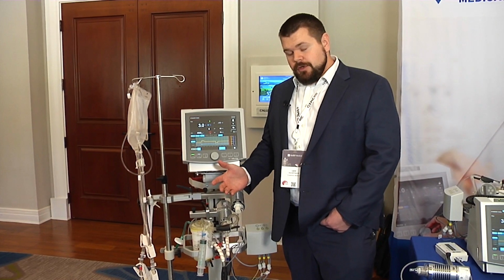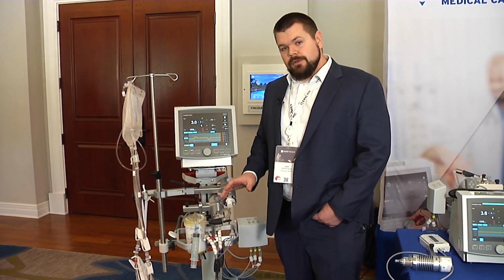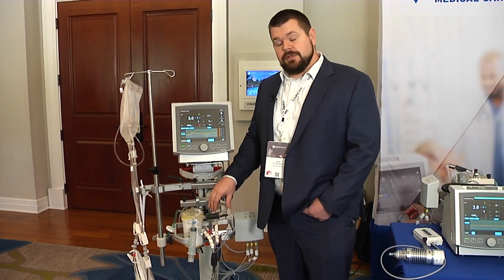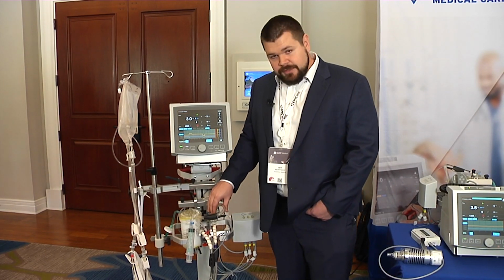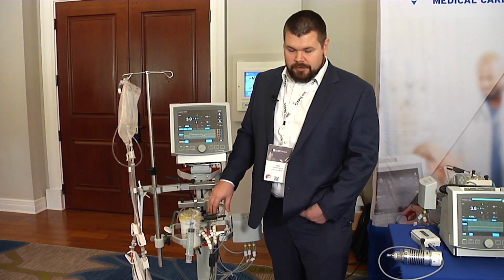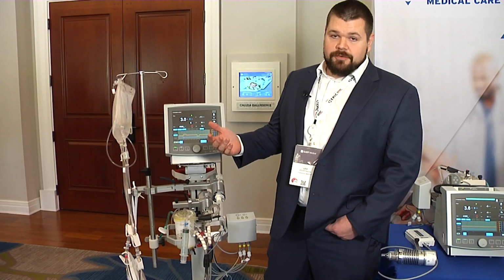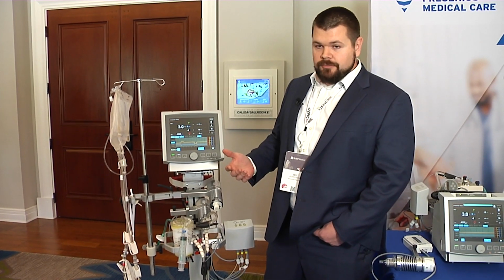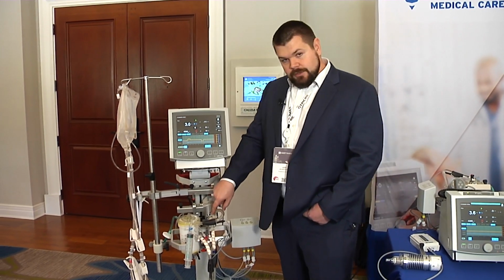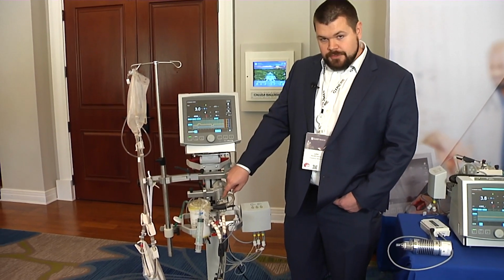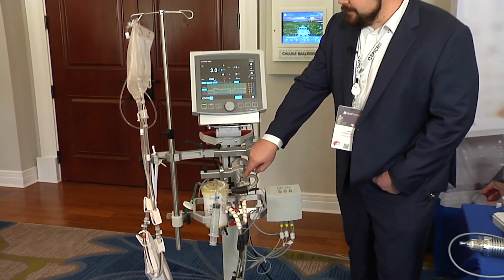One that I'll show you very quickly tends to be an Achilles heel of these non-occlusive centrifugal pumps, and that's venous air entrainment. If you get enough venous air in your system, it can result in what's called vapor lock, and that can sometimes be very difficult to resolve to get your patient back on flow. So if you zoom in here on this pump head, I'm going to entrain some air, and I'll show you how easy it is to get the pump reprimed on this system.